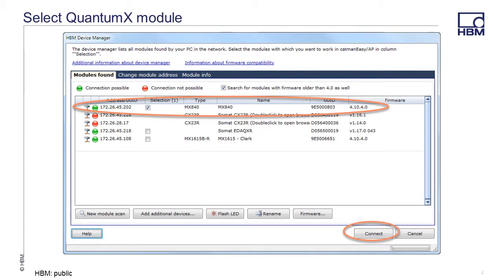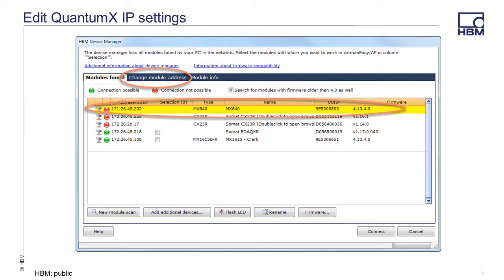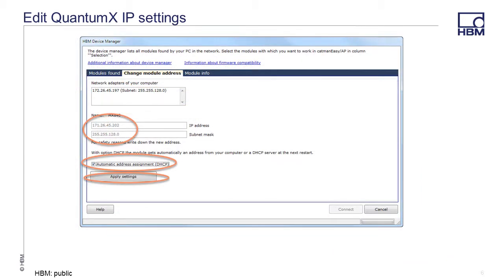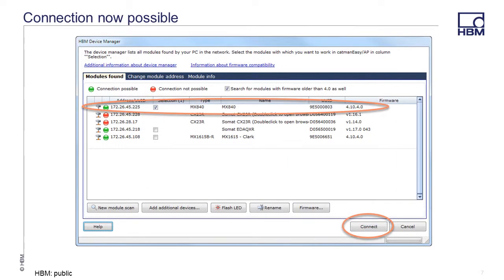If the QuantumX module you wish to connect to has a green light next to it, you can just select that module and click Connect. If the QuantumX module you want to connect to has a red light next to it, select the module and click the Change Module Address tab. Then either enter an IP address manually or select to use DHCP and click Apply Settings. After the settings have been applied, the QuantumX module should now have a green light next to it. Select the module and click Connect.